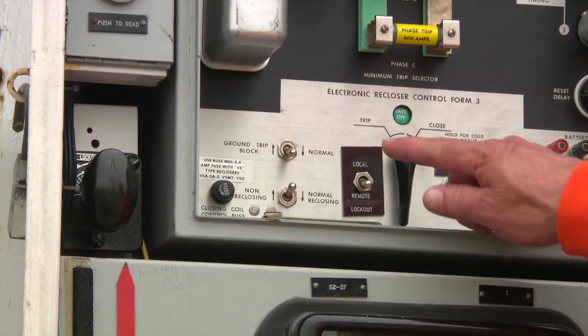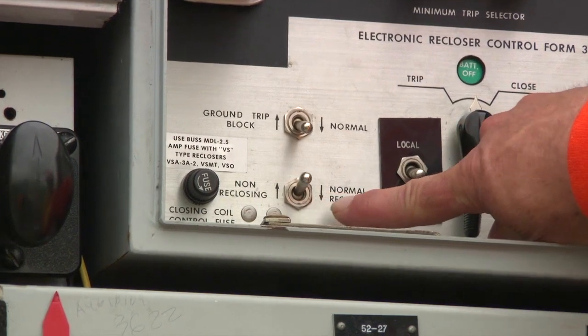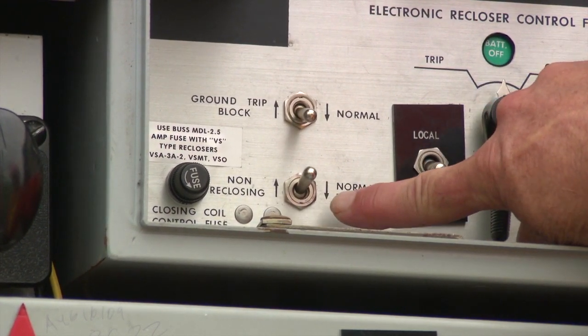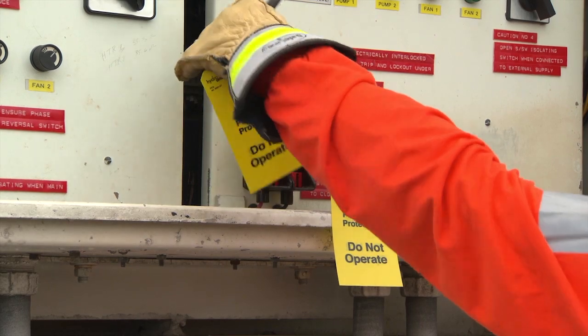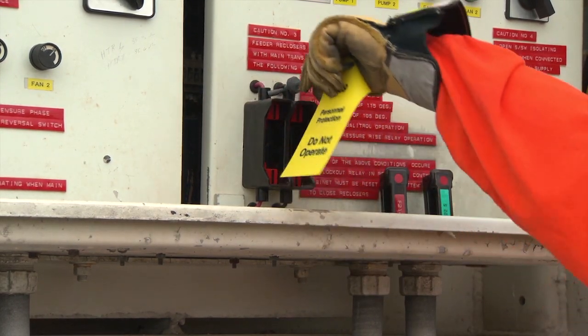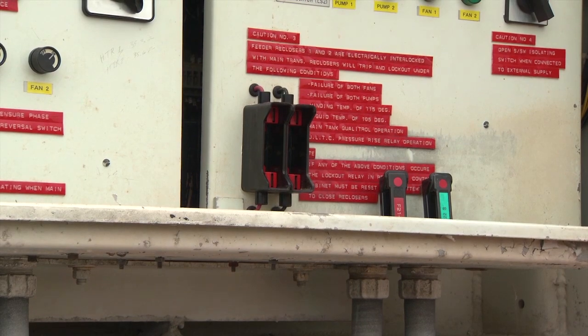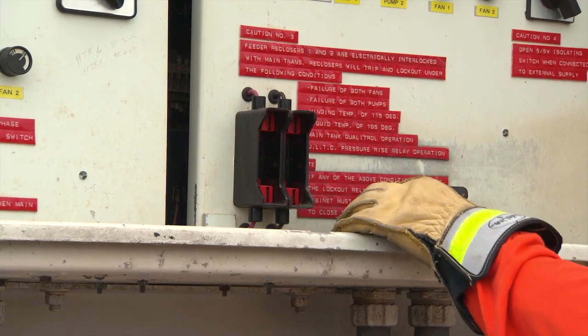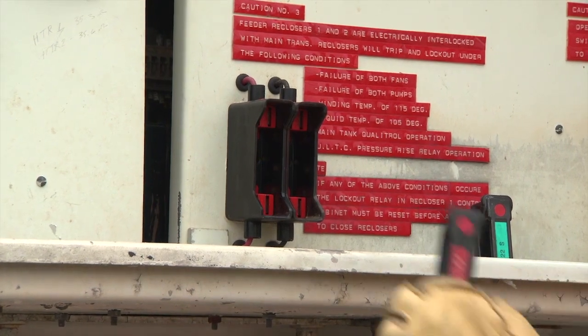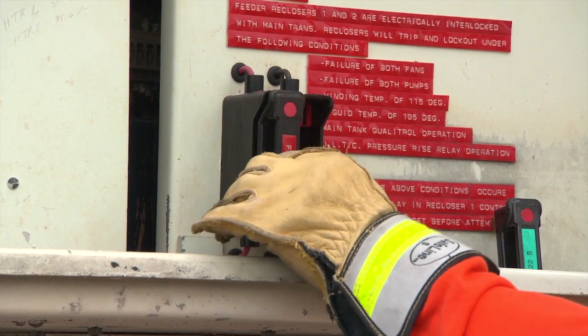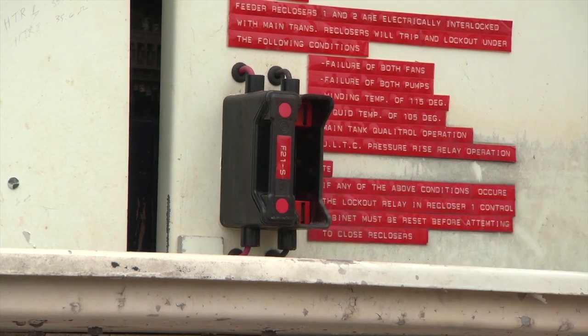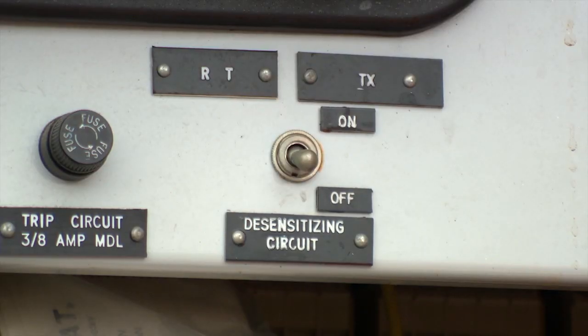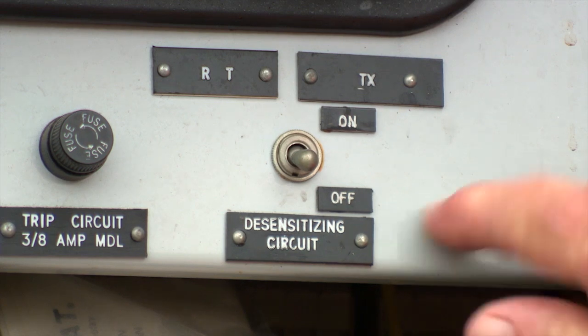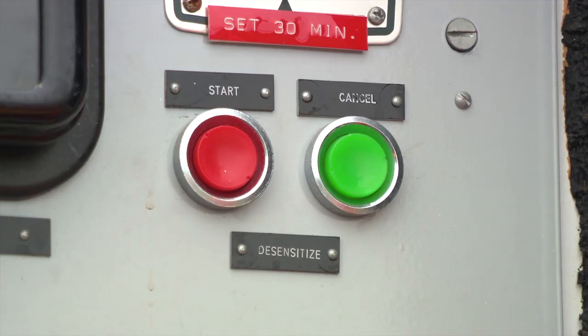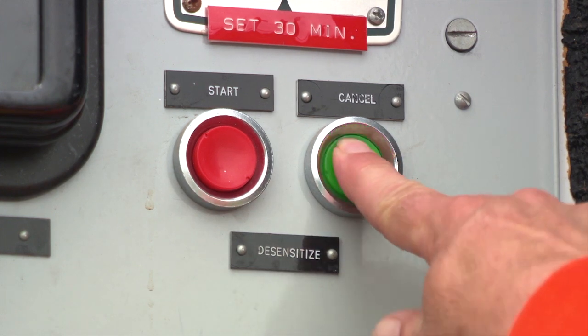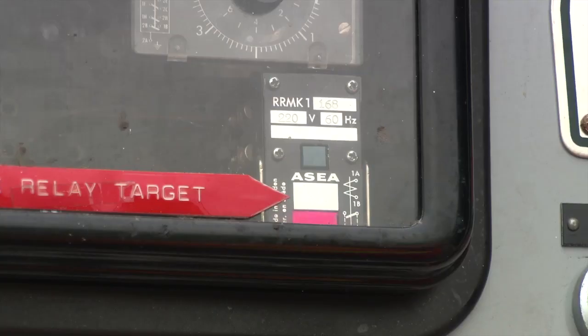Check that the MUS F1 non-reclosing normal reclosing switch is in the non-reclosing position. Remove the work protection tags from the insertion points of the recloser AC supply fuses and install the F21 and F22 fuses. This will charge the recloser springs. Turn the desensitizing relay on to ensure it is functional. Then push the desensitizing relay cancel button and reset the TX relay.